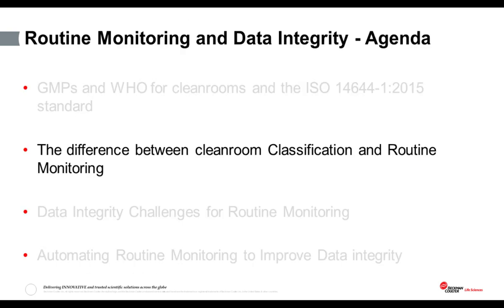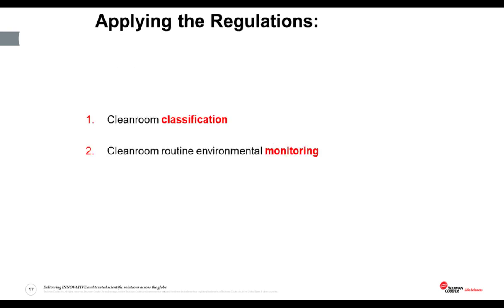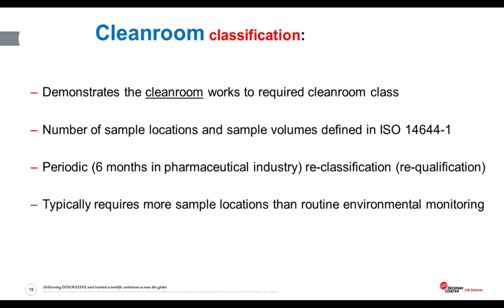So that's the rules and regulations. Let's take a look now at clean room classification and routine monitoring — two very different things. Portable particle counters are used for both applications. The classification process is defined very clearly in the ISO standard, whereas it's the responsibility of the user to define the routine environmental monitoring program specific to their own production process, product, and clean room. This absence of specific guidance for routine monitoring locations and frequencies often leads the user to wonder what they should be doing.